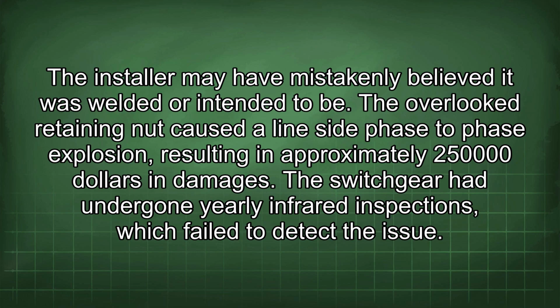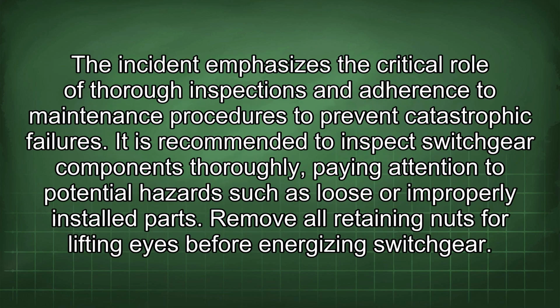The overlooked retaining nut caused a line-side phase-to-phase explosion, resulting in approximately $250,000 in damages. The switchgear had undergone yearly infrared inspections, which failed to detect the issue. The incident emphasizes the critical role of thorough inspections and adherence to maintenance procedures to prevent catastrophic failures.